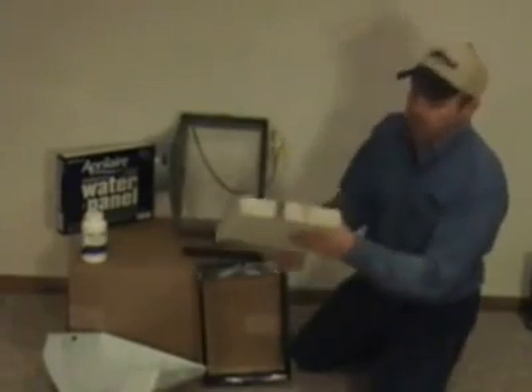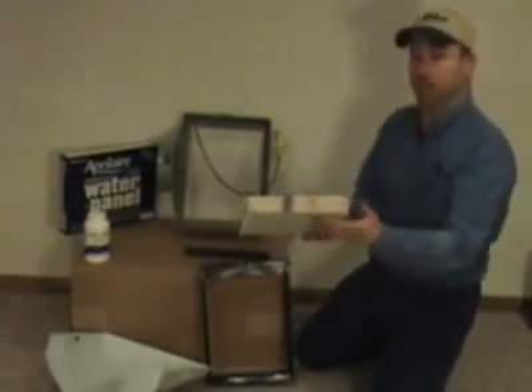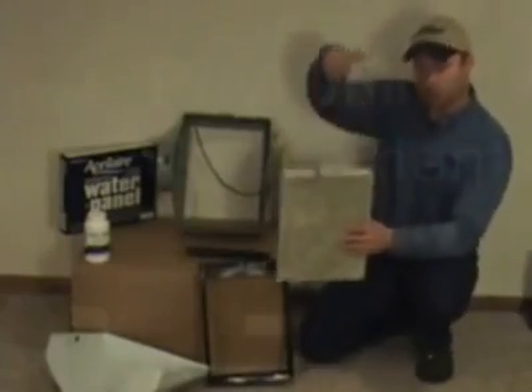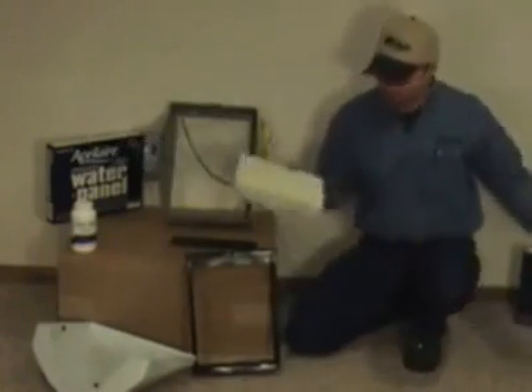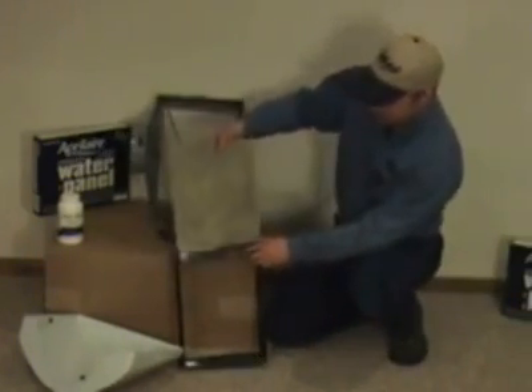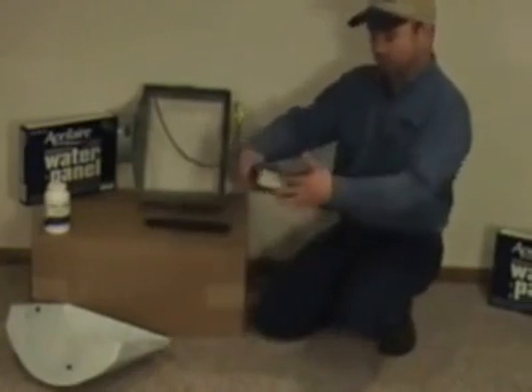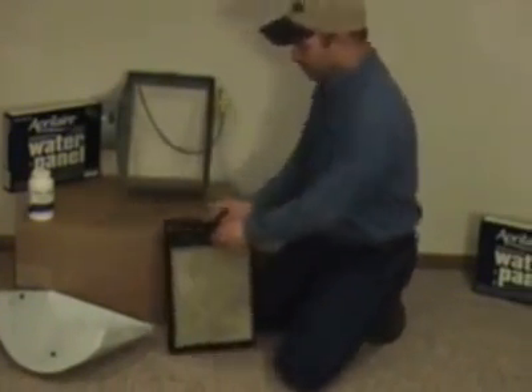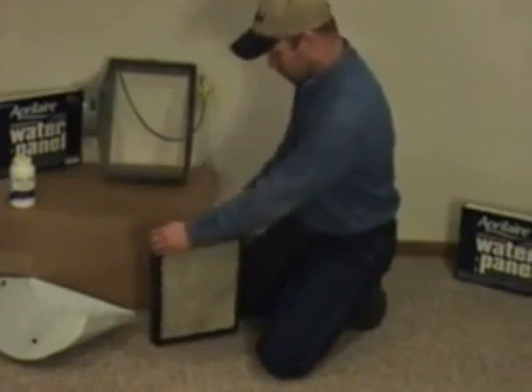These water panels typically have a black spot or a red spot on top — that's the way you want the water to be distributed down. Simply pull your new pad out of the box, slide it back in the way the old one was with that spot marker on top, and reinstall your water distribution tray.